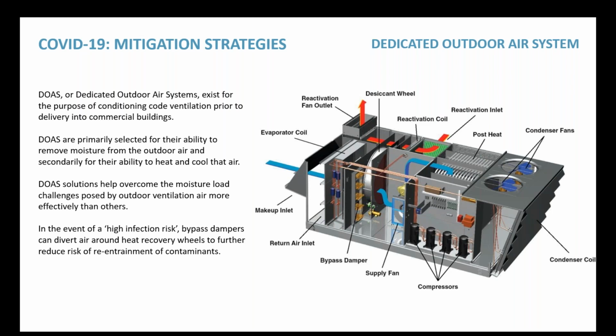Another thing that has come up quite a bit, and we see these dedicated outside air systems all over, whether in residential applications, commercial applications, etc. Dedicated outside air systems for the treatment of outside air have become quite common. And while they're great, they're bringing in 100% outside air, they're already doing that economizer function. There are specific components that you need to take great care with and pay attention to, in this case specifically the energy recovery wheels. We try to be energy conscious with the amount of energy we're using to condition outside air, and these energy recovery wheels allow us to recover a lot of energy from the exhaust airstream.